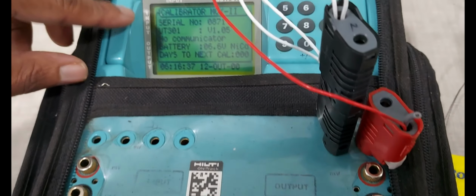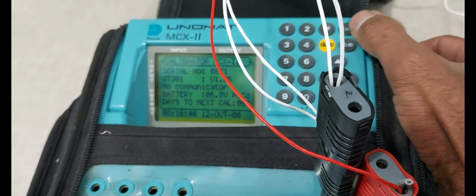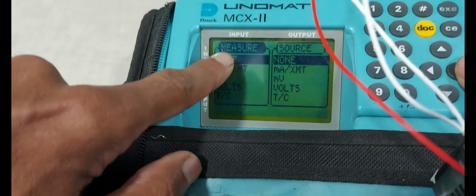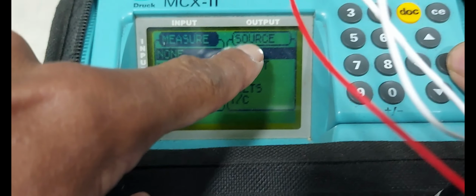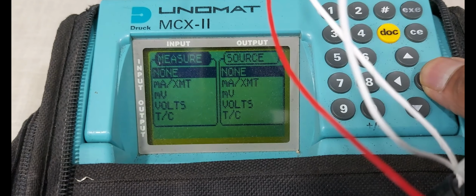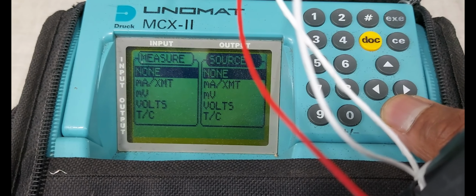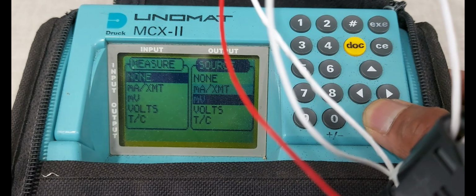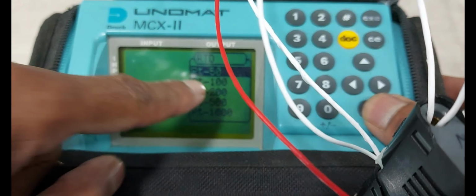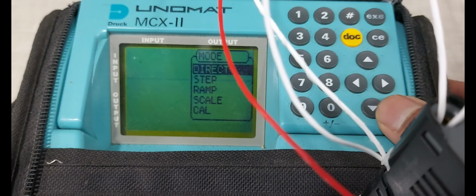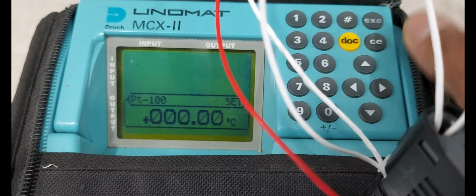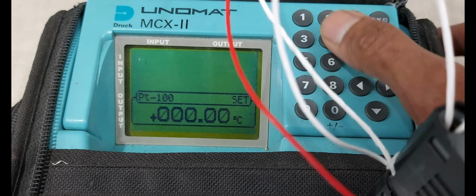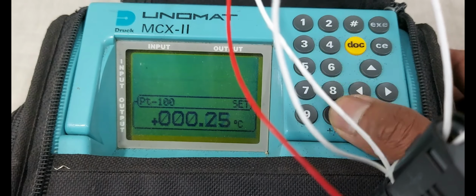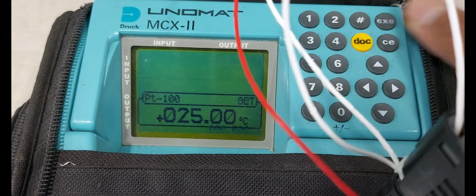Next power on the multifunction calibrator. Now it is powered on, and enter. There are two options, a measuring option and a source option. We are selecting the source option. Select it and go down. RTD, enter it. There is PT100, enter, direct, enter. Okay, now we are applying 25 degrees, enter.